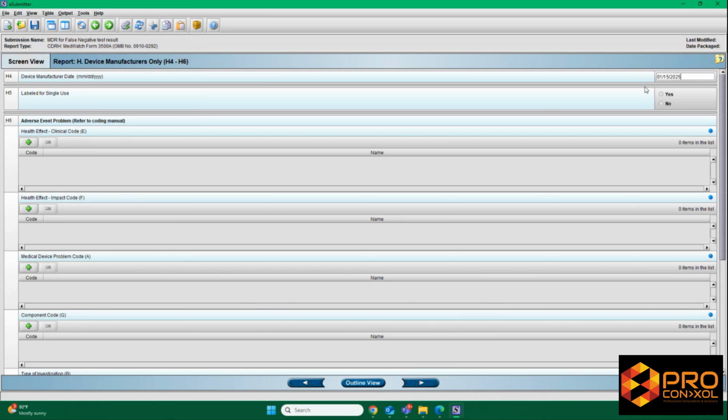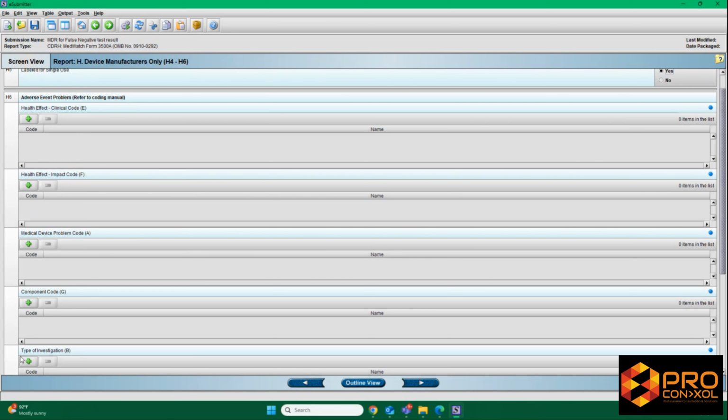H6 talks about the adverse event problem. We will select and document the appropriate problem codes from the FDA coding manual to classify the reported issue. And I will show in detail how to find those codes and how we can correlate those FDA codes with eMDR codes in this video.